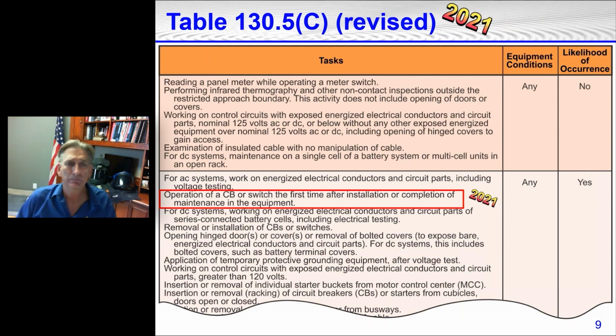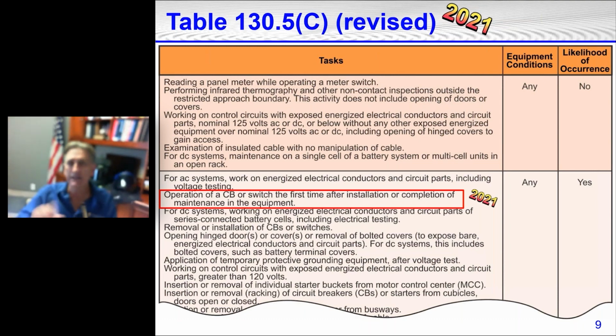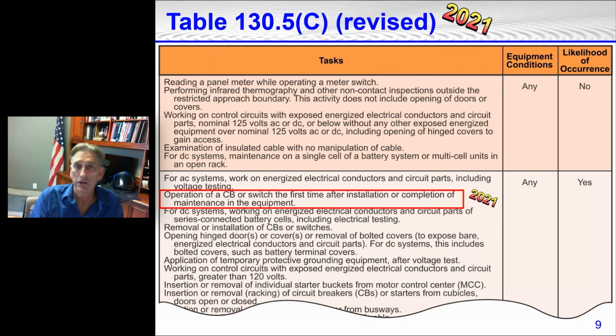For example, looking at the upper left, the very first one at the top: reading a panel meter while operating a meter switch. You've got a piece of switchgear. It's all closed up. You've got a display on the front that you can punch in numbers on and find the information that you want. You want current on phase A, current on phase C, total kVA, total kW. The equipment is all closed up, and you're in front of it just punching in information. So the likelihood of occurrence is no. That means you do not have to be wearing arc rated PPE when you're doing the first items on the list. Let's look down to the next group.